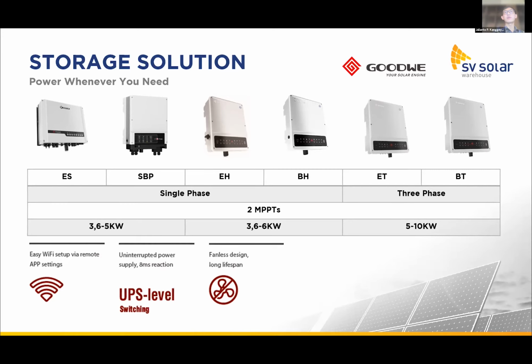For the three-phase system, we have the ET and BT series. Like single phase, ET is the all-in-one hybrid inverter and BT is the AC retrofit inverter. The power rating for the three-phase inverters is 5 to 10 kilowatts, and all of them come with 2 MPPTs. Some product features for this storage solution are easy setup via remote and application. For backup, they have UPS-level switching, which means when the power grid fails, the inverter needs less than 8 milliseconds to switch to the batteries.